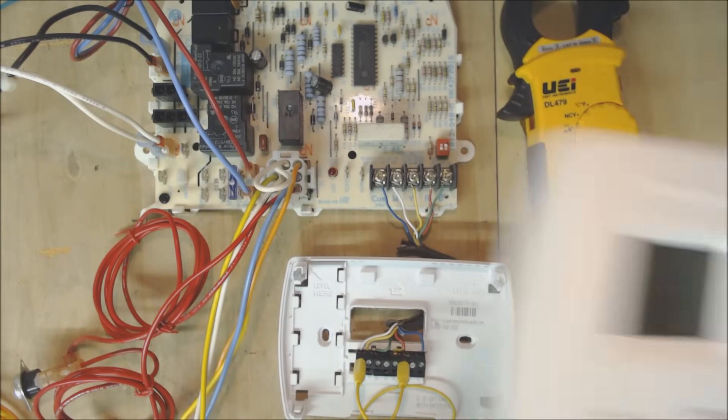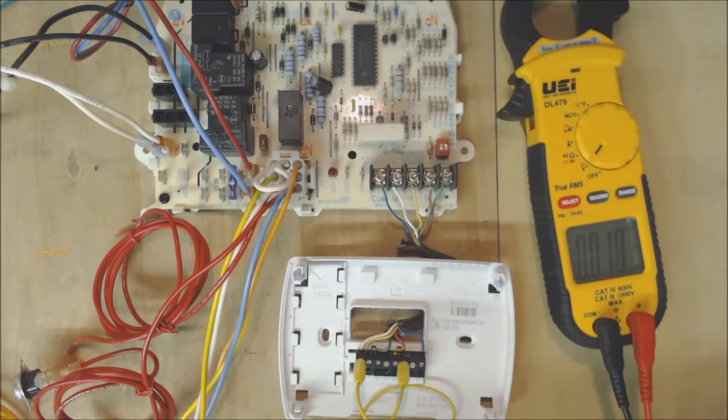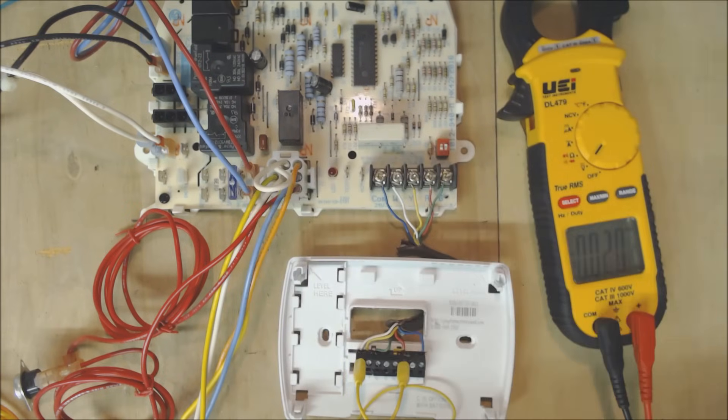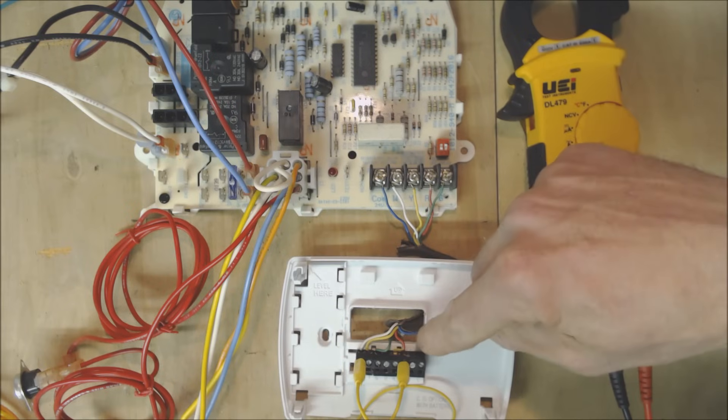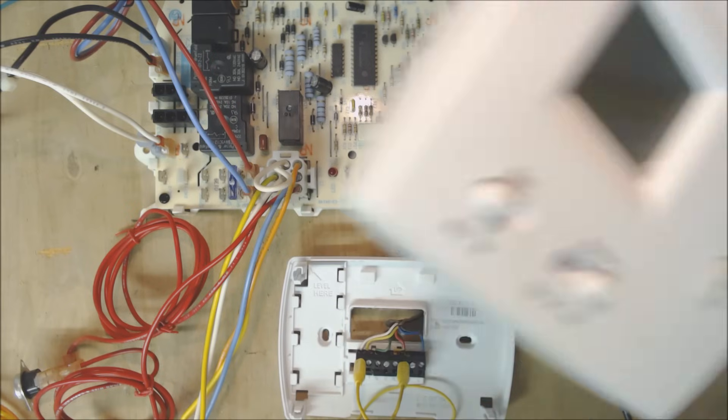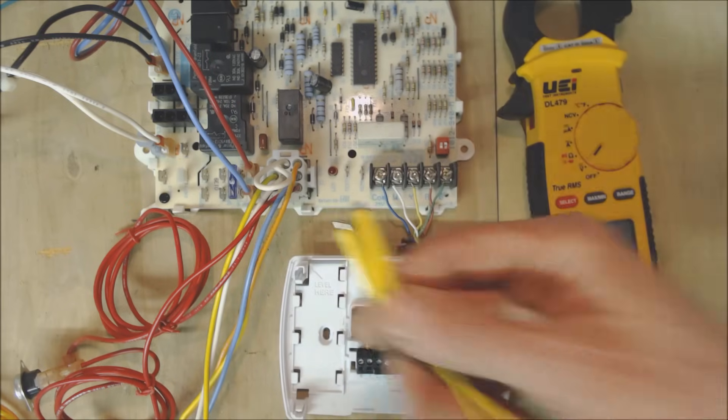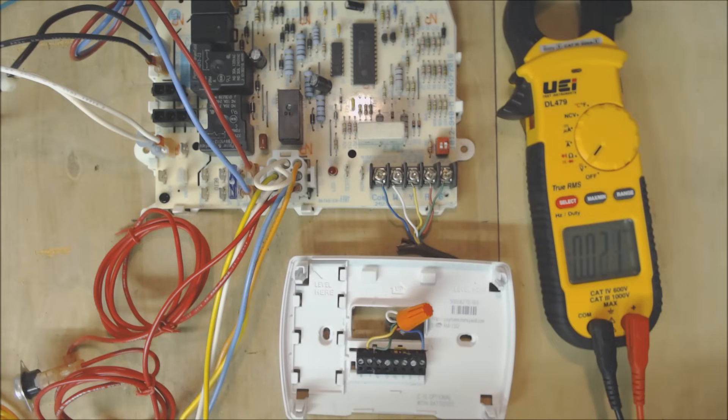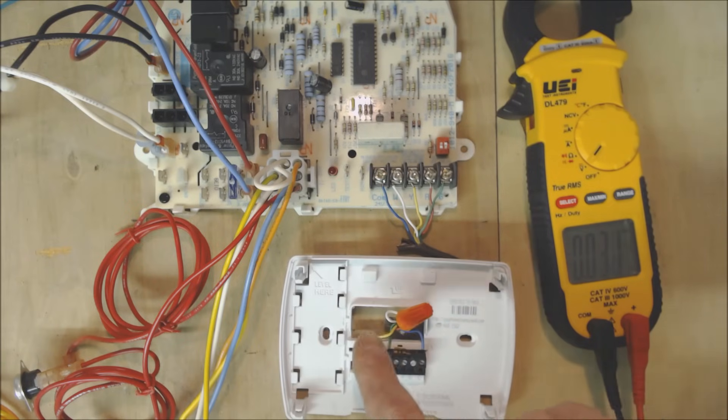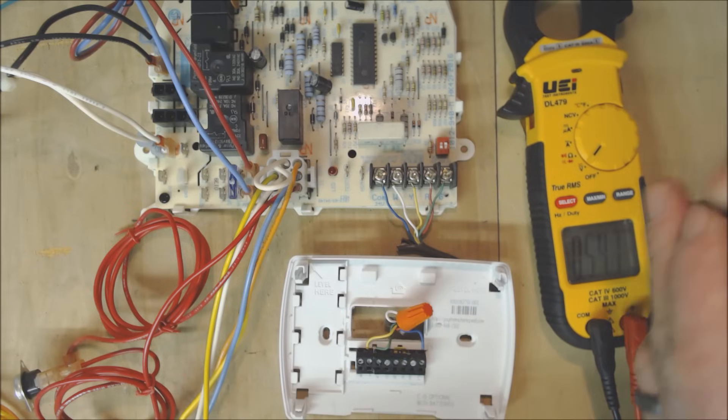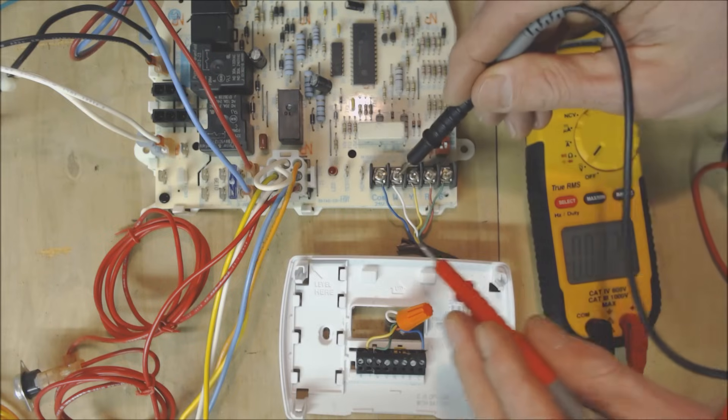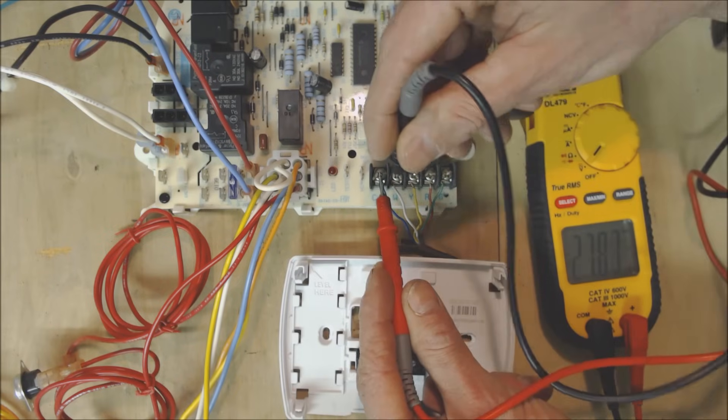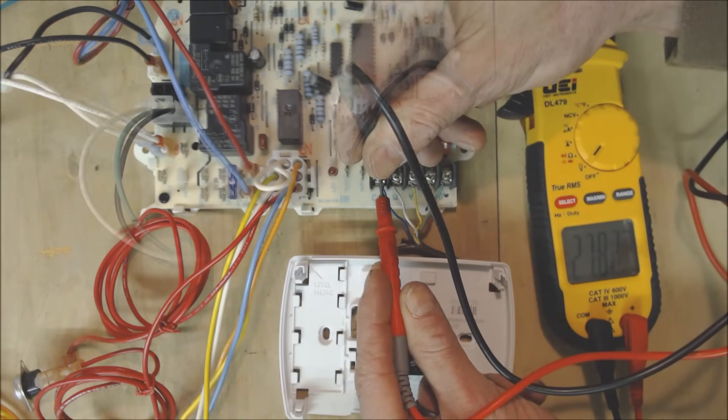That tells you that the thermostat face is the problem. If we actually took the face off and we jumpered inside the thermostat face from R to W then you know that this was the problem. So if you don't have mag jumpers what you could do is turn the power off and then you could jump the R and the W together with a wire nut and then you can go ahead and check inside your furnace at your control board for W to C and you see that we have 27 volts right now.